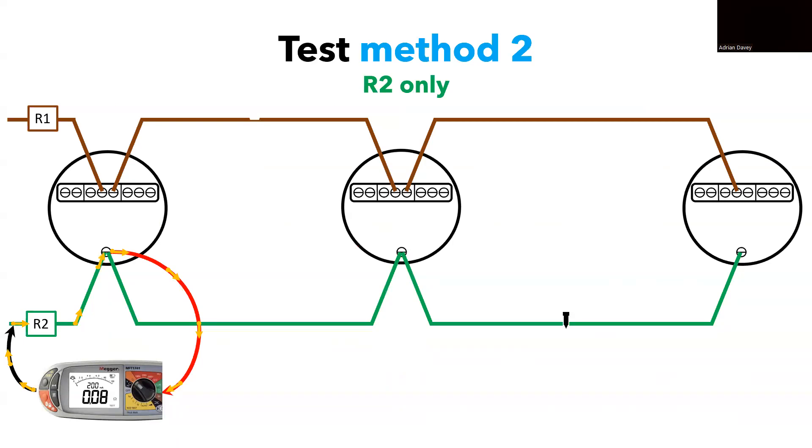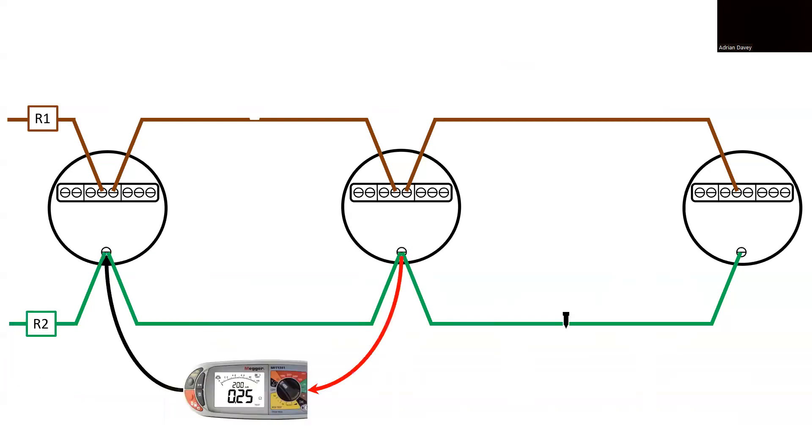Starting at the supply, you would test the feed into the first light yielding a value of 0.08 ohms. This suggests that the fault is not in this segment of the circuit. For added confirmation for the test results, you can again refer to table I5 in the on-site guide and calculate the expected value. Upon confirmation, you can progress to the next section of the circuit and assess the feed to the next light.